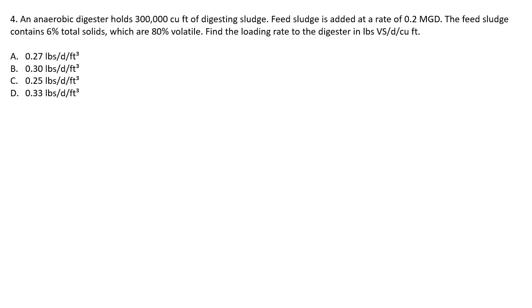Question four: an anaerobic digester holds 300,000 cubic feet of digesting sludge. Feed sludge is added at a rate of 0.2 MGD. The feed sludge contains 6% total solids, which are 80% volatile. Find the loading rate to the digester in pounds volatile solids per day per cubic foot.